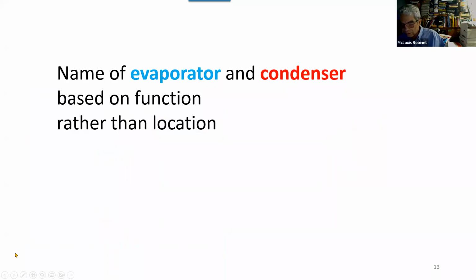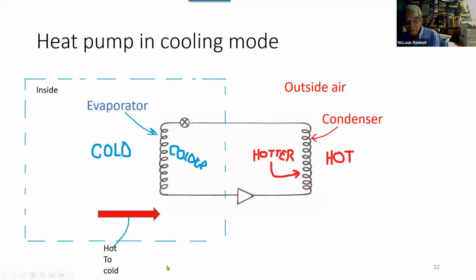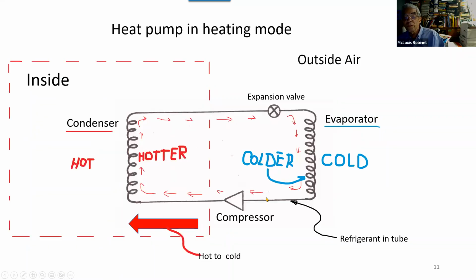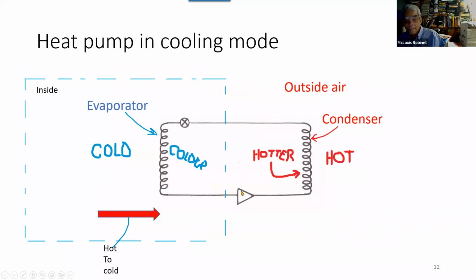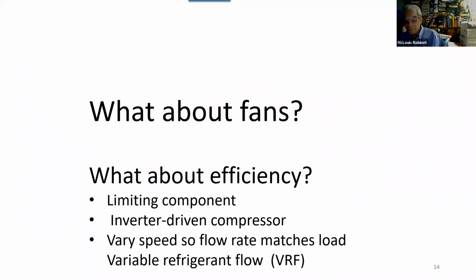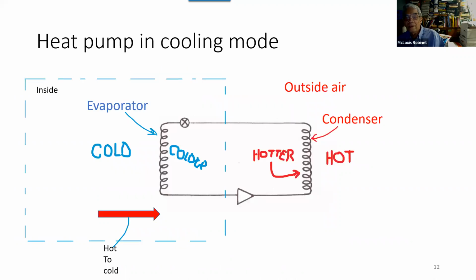You notice also that the direction of the flow is different. In reality, we wouldn't be physically reversing the direction of the compressor. We use a simple plumbing system called a reversing valve. Okay. So what about fans? Again, this is the basic fundamental system, but in a real system, you have a fan here and there to move the air.